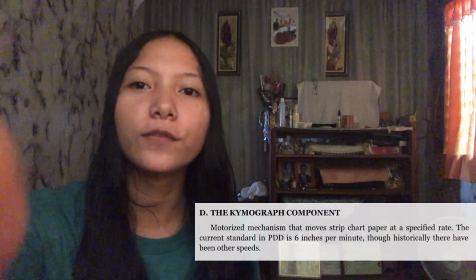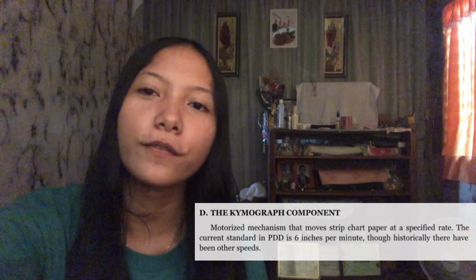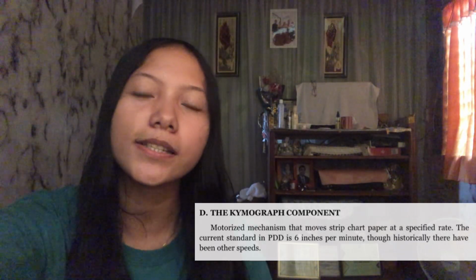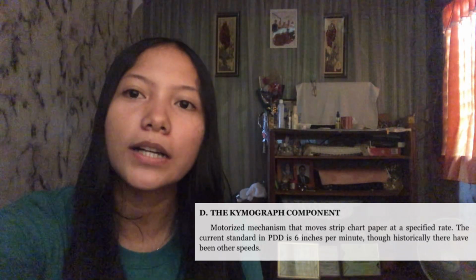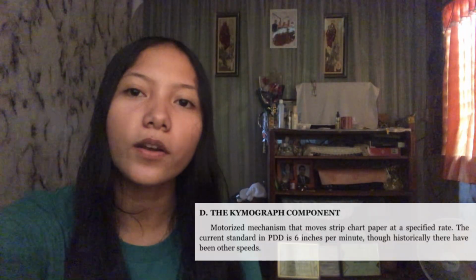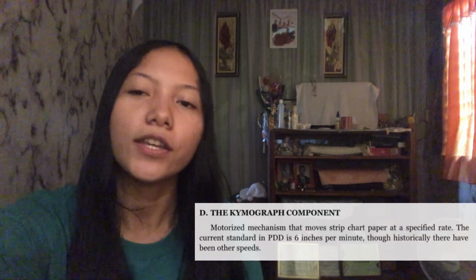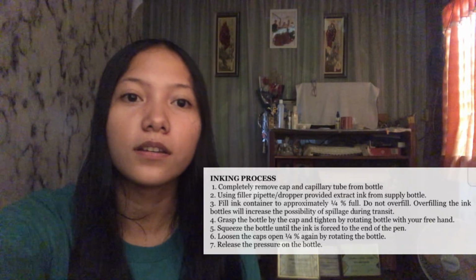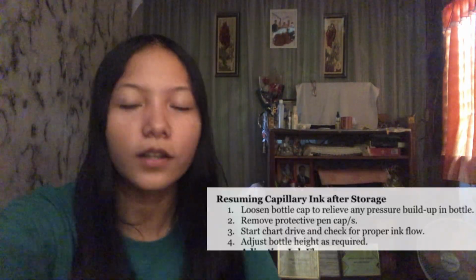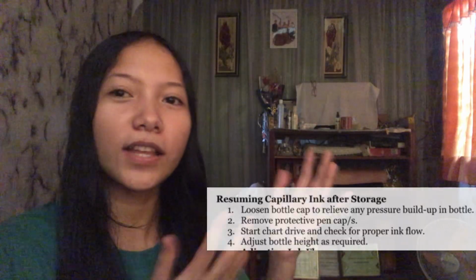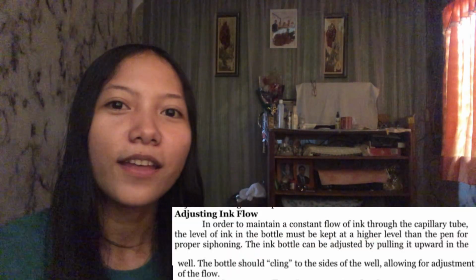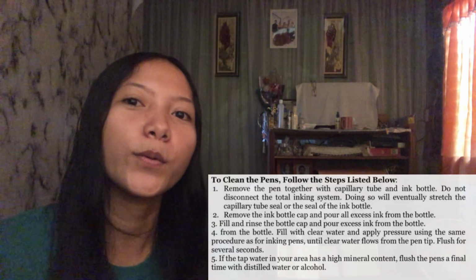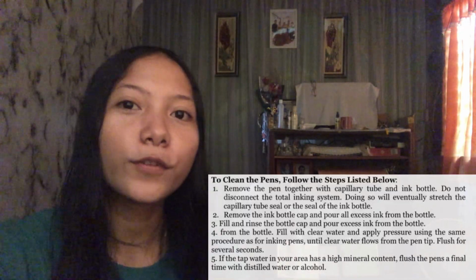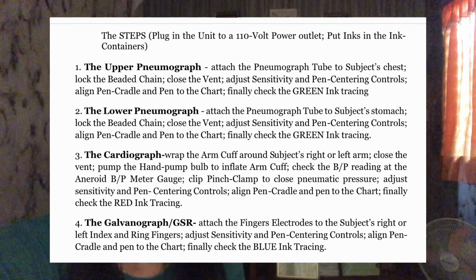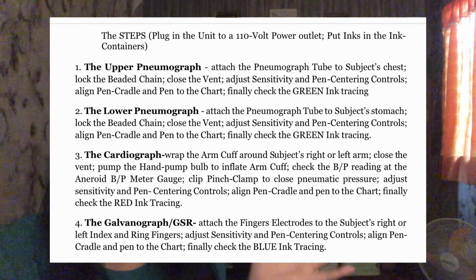Now let's move on to the fourth component. We have the kymograph, and that is a motorized mechanism that moves strip chart paper at a specified rate. So the current standard in PDD is 6 inches per minute, though historically there have been other speeds. So I will just flash here the inking process, the resuming capillary ink after storage, and adjusting the ink flow for you to know what are the procedures. And another information to clean the pens, just follow the steps listed here below.